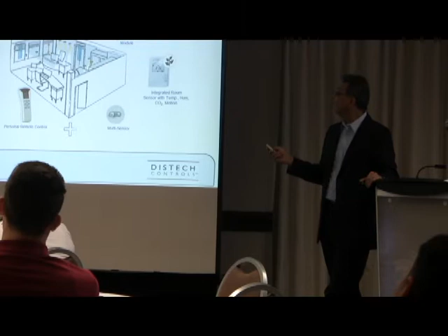And we've also got this lighting extension module. Lighting control has been around for a number of years, but we're not doing it at the panel-based level, although we do have a panel-based solution - we're doing it at the ballast level. We're using DALI, another open protocol, which is digital addressable lighting interface, to accomplish that. We'll get a little bit more into that.